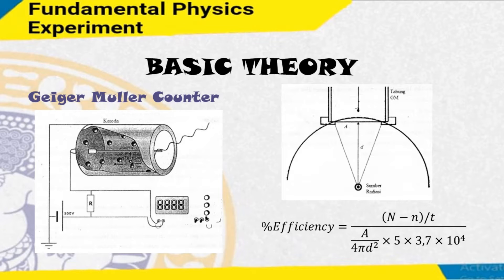The Geiger-Muller tube is filled with an inert gas such as helium, neon, or argon at low pressure, which is subjected to a high voltage. The tube briefly conducts an electric charge when the particles or photons of incident radiation make the gas conductive by ionization. The ionization is significantly amplified in the tube by the Townsend discharge effect to produce an easily measured detection pulse, which is fed to the processing and display electronics.